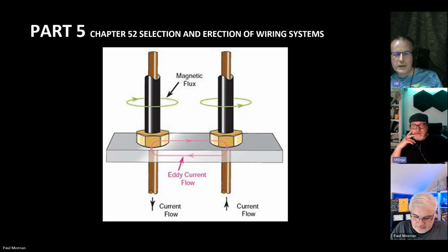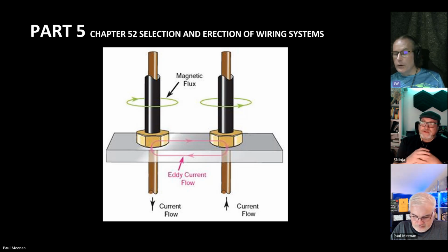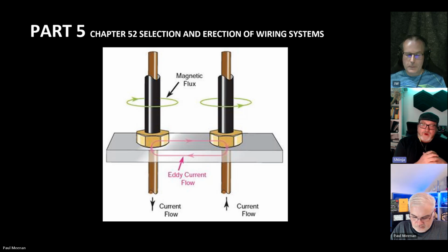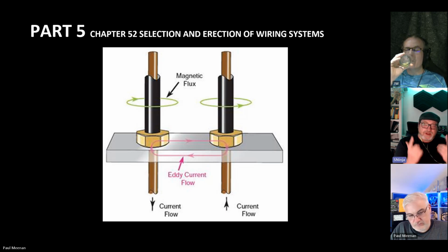Yeah. The only problem I see with this is that if they've tested it at 50 hertz AC, that's great. But in the real world, what if it's not all 50 hertz? What if there's a load of harmonics in there at much higher frequencies? Then the heating effect is going to be considerably different. Generally, if you increase the frequency, the heating is increased. So an IB of 200 amps may not represent the heating that you see. If you've got harmonic current there, it's going to be much larger.